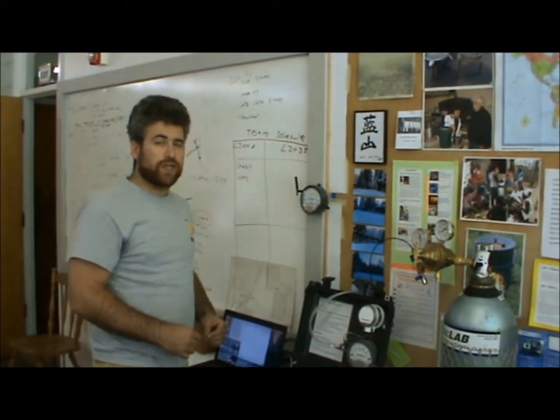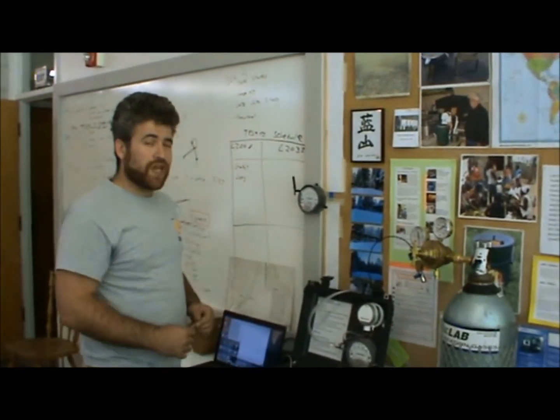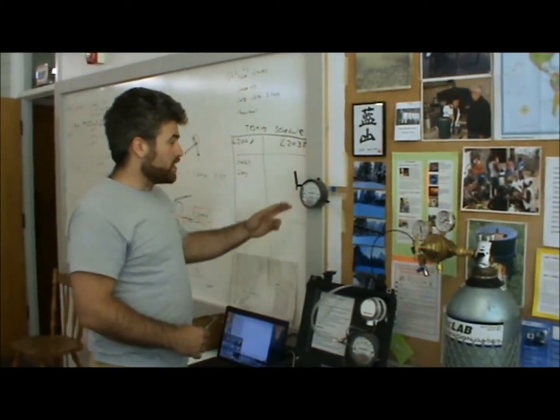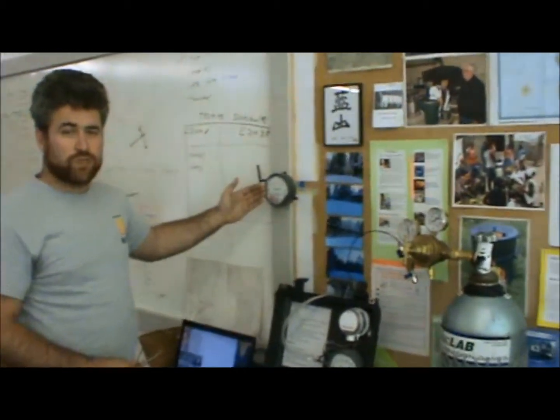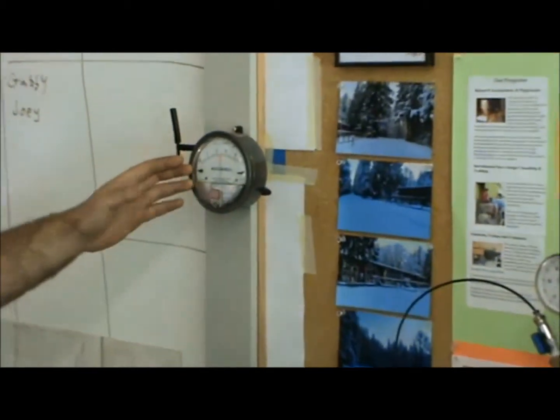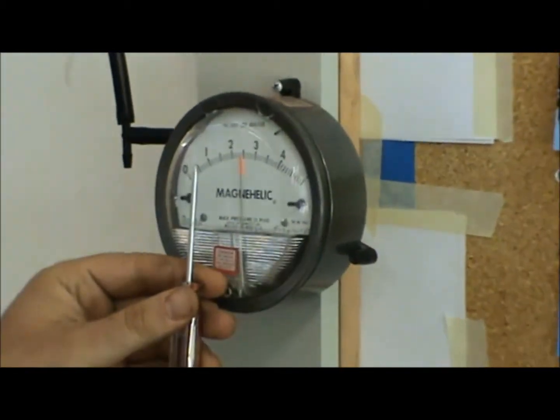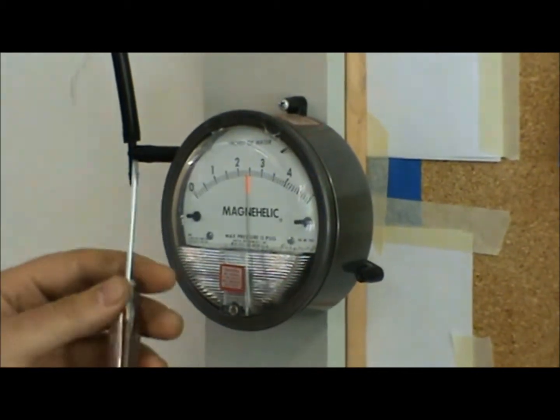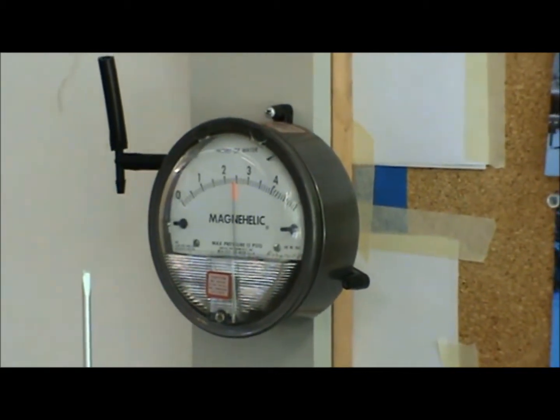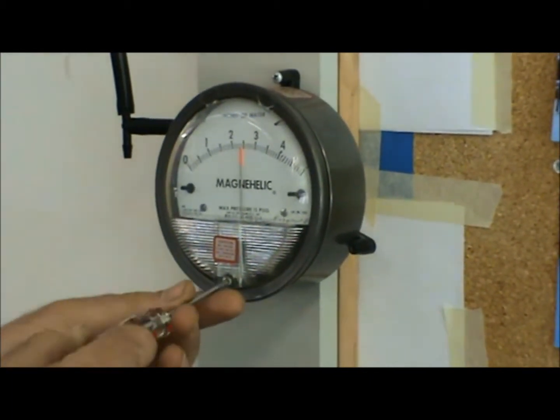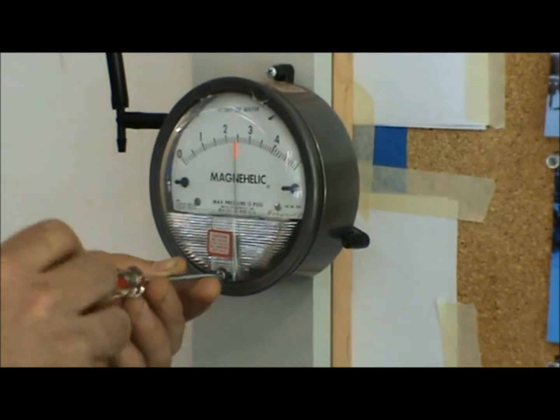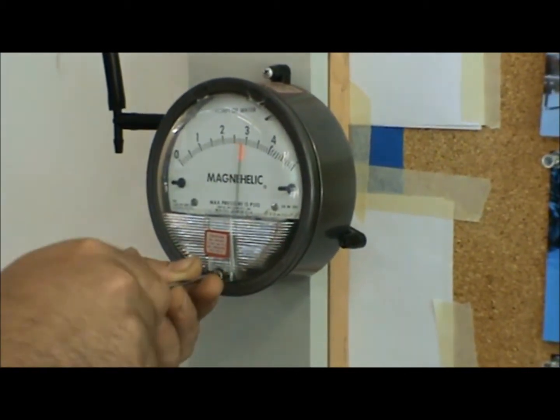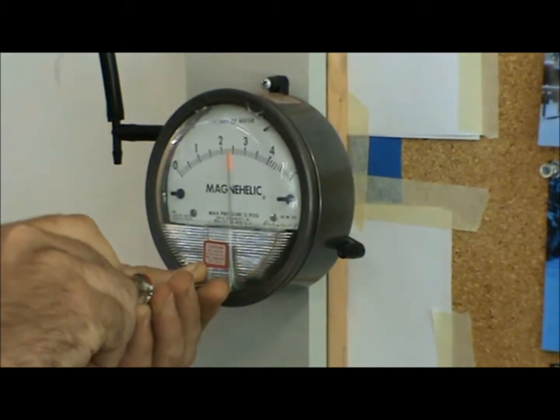Alright, so we have our 10 minutes of background data, or 600 seconds according to Tera Term. If it's a little longer, that's okay. More background is always good. You just want at least 10 minutes. So before we get this gas running, we want to take a look at our magnehelic gauge to make sure it's ready to go. You'll notice that our needle here is standing straight up, and that's good. If it's not, we can adjust it using this small flathead screwdriver and this screw down at the bottom of the magnehelic. We can adjust it till it's actually straight up by turning the screwdriver back and forth.